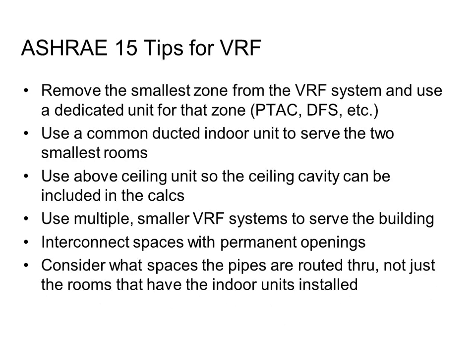And then let me just leave you the final note on that. It's not just which zones have an evaporator coil in them. It's which zones have any portion of the refrigeration system in them. So if I decide to take my refrigerant pipe and cut it through the storage room in order to get it over to that other office over there, that storage room is now part of the system. What's the cubic volume of the storage room? It's now a critical zone that I have to pay attention to. So it's not just where the indoor units are located. It's where indoor units are or piping goes through those spaces.